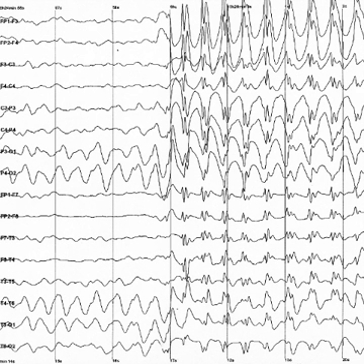In conventional scalp EEG, the recording is obtained by placing electrodes on the scalp with a conductive gel or paste, usually after preparing the scalp area by light abrasion to reduce impedance due to dead skin cells. Many systems typically use electrodes, each of which is attached to an individual wire. Some systems use caps or nets into which electrodes are embedded. This is particularly common when high-density arrays of electrodes are needed. Electrode locations and names are specified by the International 10-20 system for most clinical and research applications.